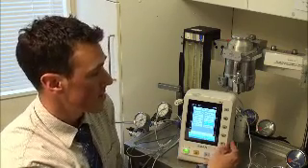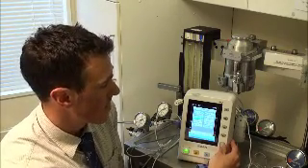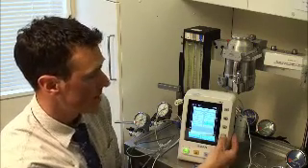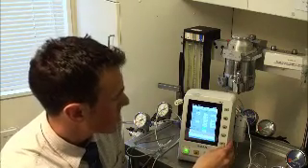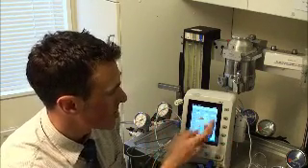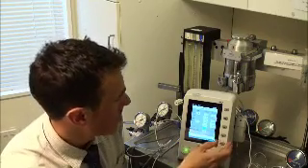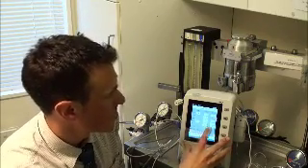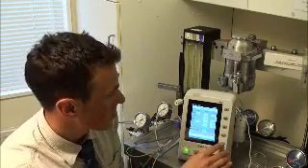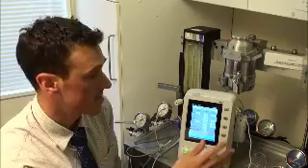To check the alarm setup, scroll down through the menu until Alarm Setup is highlighted and select. You will be able to see that the end tidal CO2 alarm is on for values between 60 and 20. Similarly, the pulse rate for values between 160 and 75. If you are happy with these, then scroll down to Exit and select.